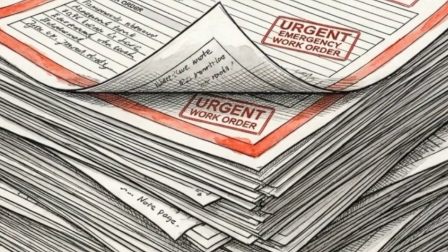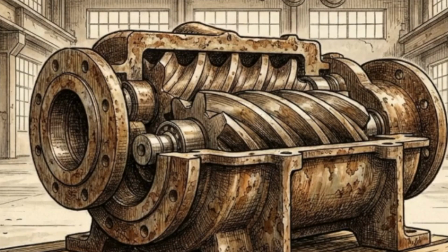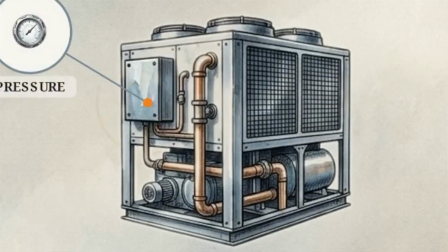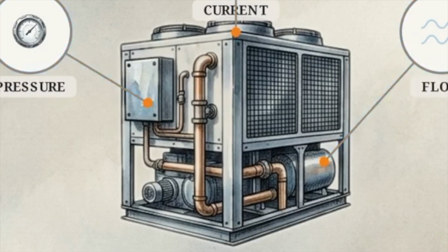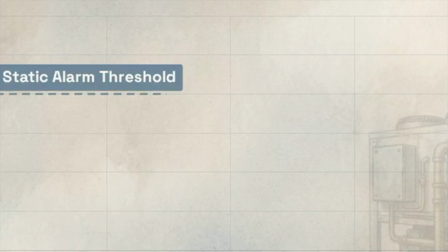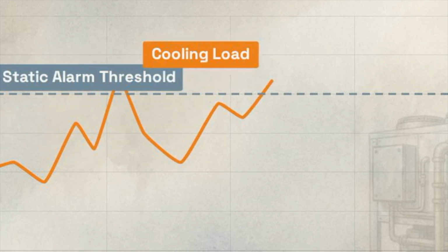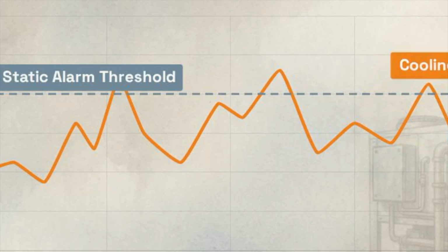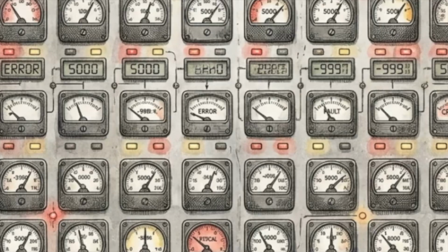Operating this reactively carries a steep penalty. An undetected leak leading to a sudden trip often results in an $85,000 emergency compressor replacement, plus the total cost of facility downtime. Upgrading the system with a continuous monitoring hardware array, installing pressure transducers, current transformers, and flow meters, costs a fraction of a single mechanical failure. However, setting static threshold alarms on these new sensors fails in practice. Industrial chillers are highly dynamic systems that continuously adjust to shifting cooling loads. Hardware alone is insufficient. Without the correct algorithmic lens to interpret the data, adding more sensors simply creates unreadable noise.